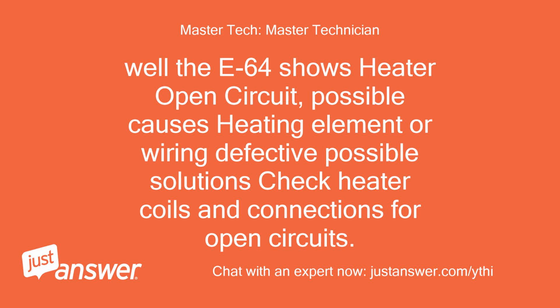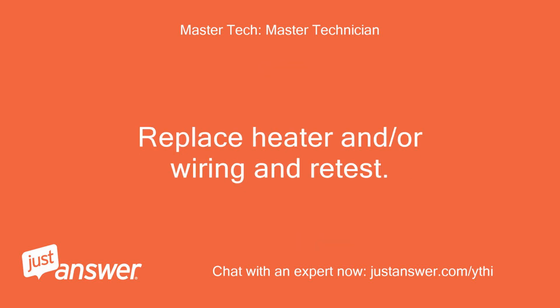Well, the E64 shows heater open circuit. Possible causes: heating element or wiring defective. Possible solutions: check heater coils and connections for open circuits, replace heater and/or wiring and retest.